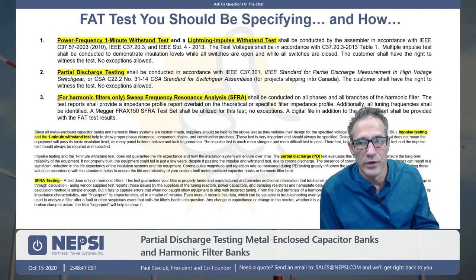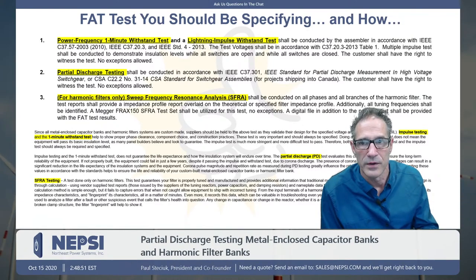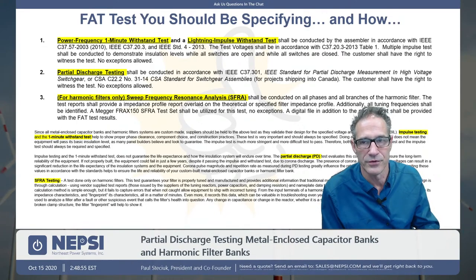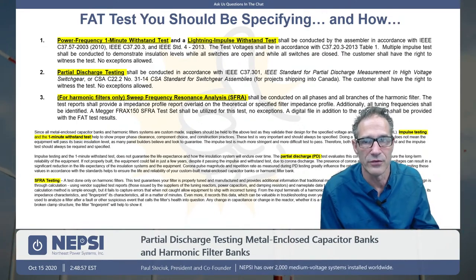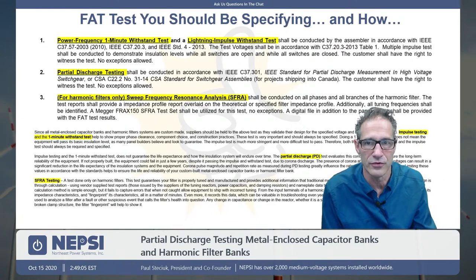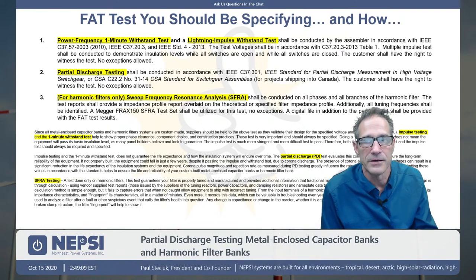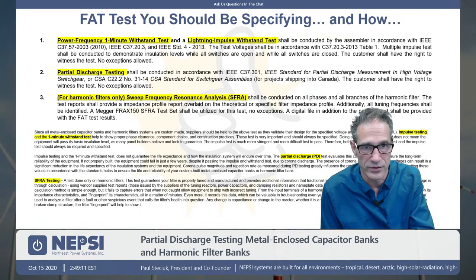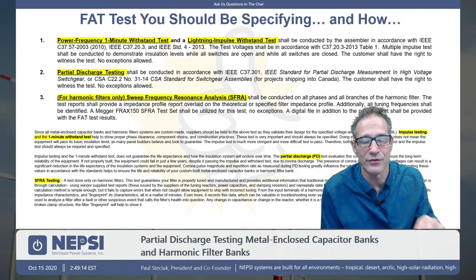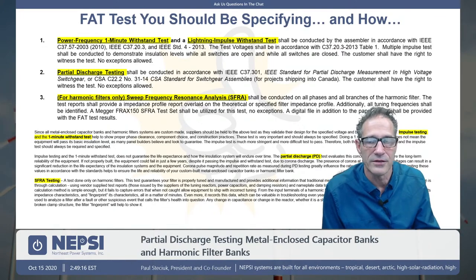So we have done three different main tests in the last few weeks. Power frequency withstand test we didn't do, but basically that's bringing the system voltage up to a withstand value based upon the standard that you're designing for, whether it's IEC, CSA, or IEEE. Lightning impulse test, we say, is very important because it helps to confirm the impulse rating of your equipment. Partial discharge testing we did today is really to confirm that your equipment will last for 20 years, and that's what that test is all about.